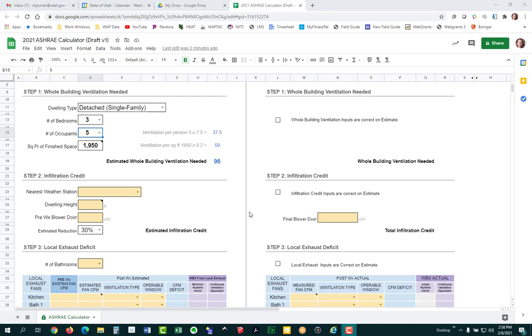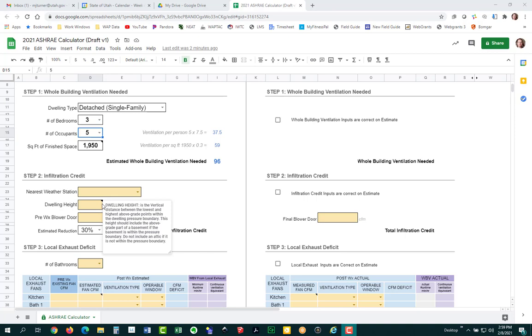For step two, we calculate the infiltration credit. The ASHRAE standard says if you measure how leaky the house is, you could get an infiltration credit. If you have a really leaky house with a lot of natural infiltration, you might not need any mechanical ventilation. To calculate this, we need to know the nearest weather station to use its weather and wind shielding factor, and the dwelling height so it can account for stack effect.